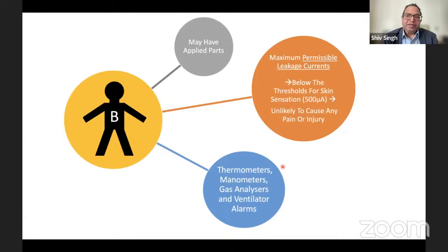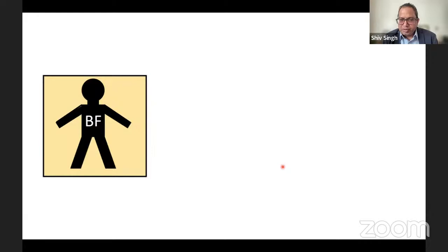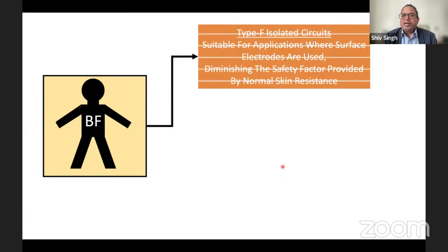Examples of this kind of equipment are thermometers, manometers, gas analyzers, and ventilator alarms. Now, these can be type B. But what about BF? If you see a man or a body inside a box, that is called type BF. So how is it different? Well, it uses a type F isolated circuit. F stands for floating, so body floating. And this is suitable for applications where surface electrodes are used.